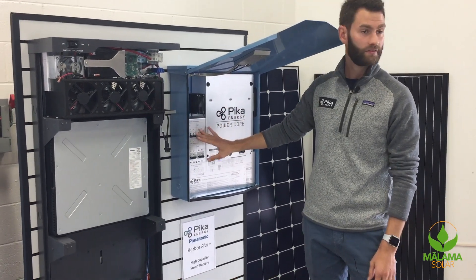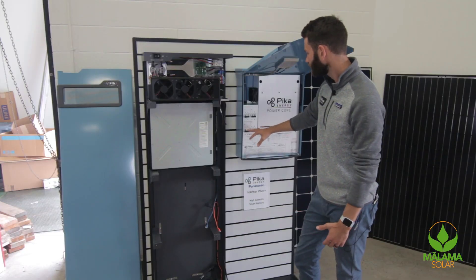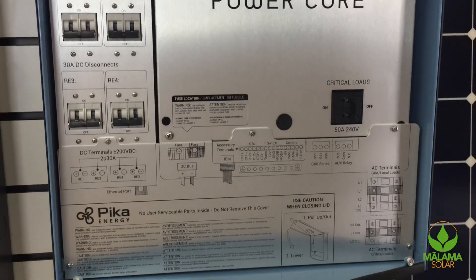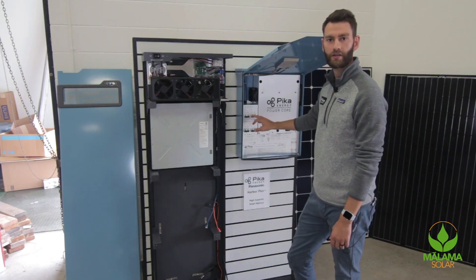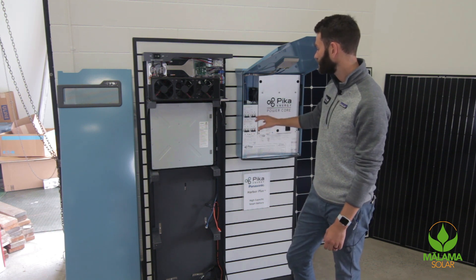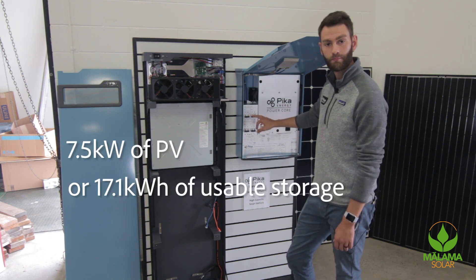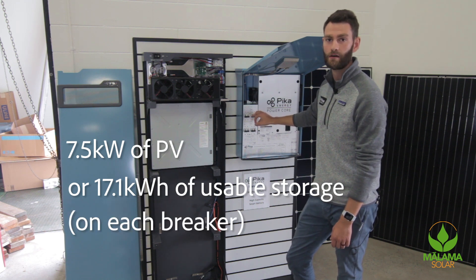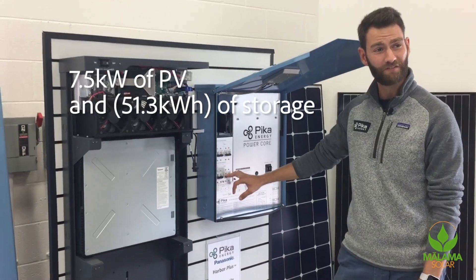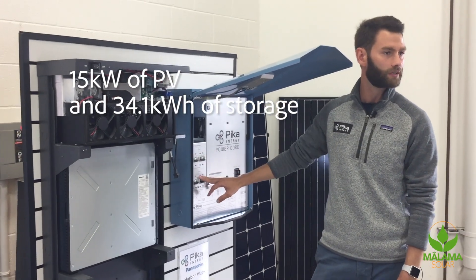On the left-hand side here — this really makes Pika Energy unique — we have four 30-amp DC breakers. That means we have four DC inputs where you can connect either up to one Harbor Smart battery or three of our substring optimizers. Each substring optimizer outputs around 2.5 kilowatts, so on each one of these breakers you could technically put up to 7.5 kilowatts of PV or up to 17.1 usable kilowatt hours of Panasonic lithium-ion storage. So you could do 7.5 kilowatts of PV and three Harbor Plus batteries, which would be 51 kilowatt hours of usable storage, or 15 kilowatts of PV with 34 kilowatt hours of storage.